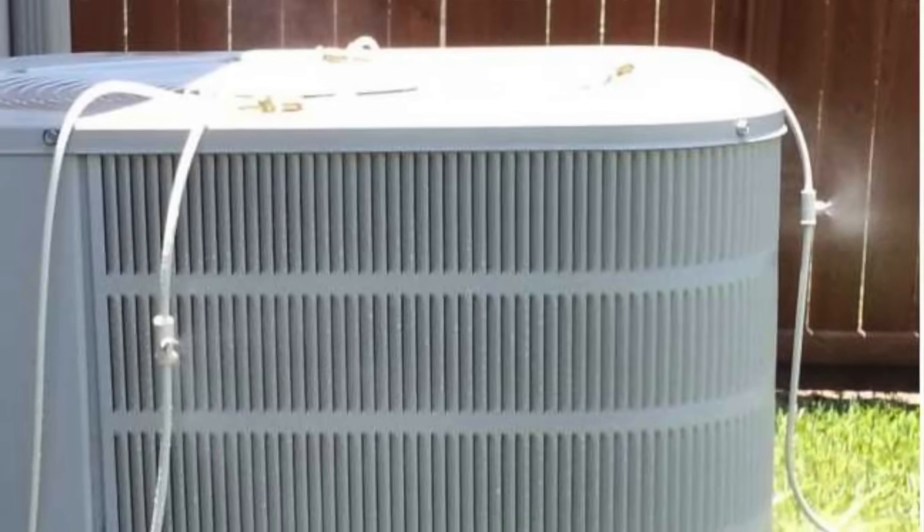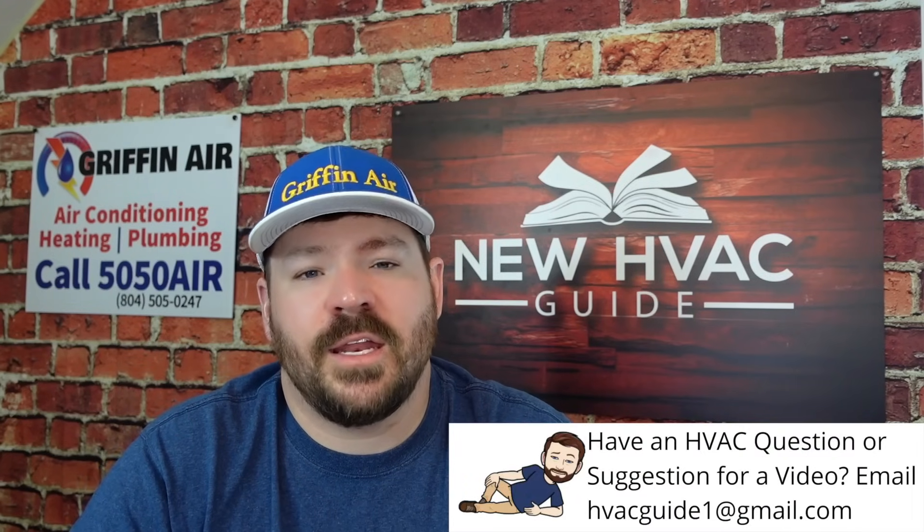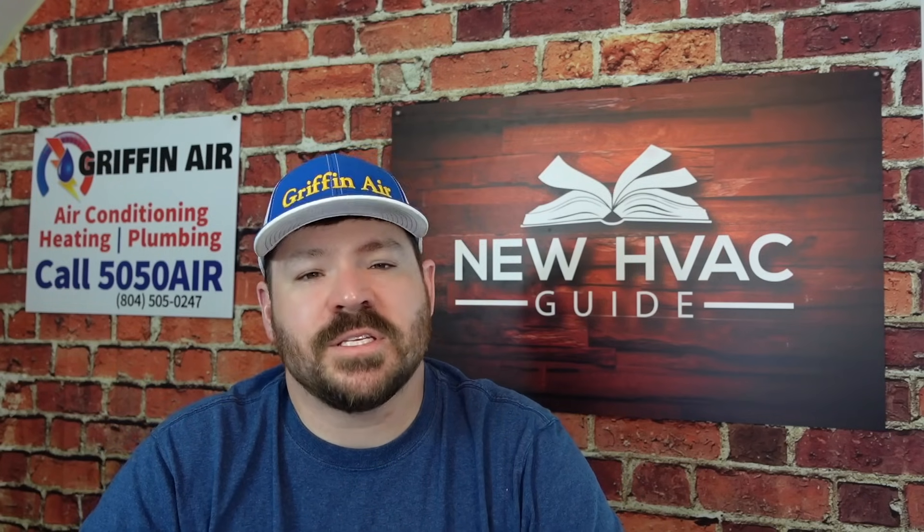There's also a product that can mist the heating and air system — I'll link to these products in the notes. We don't really see misters in markets with heat pumps or colder weather, but in really hot climates some installers use misters on the coil, allowing it to operate at much higher capacity. By cooling the coil with mist, you're essentially applying the same technology as a cooling tower on a commercial building — you get wet coils that lower head pressure and allow the system to operate even better. That said, I wouldn't install any of these products without checking with your local HVAC pro first and getting their opinion.